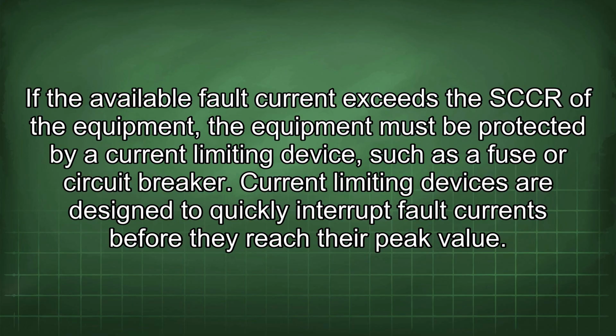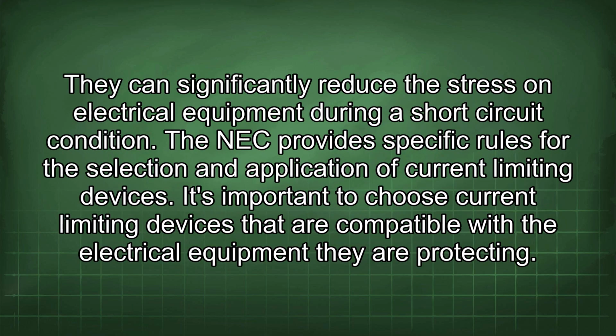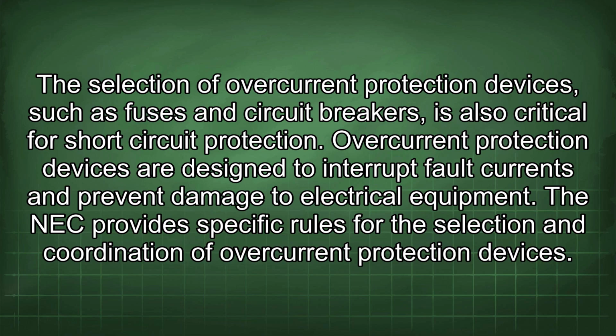Current limiting devices are designed to quickly interrupt fault currents before they reach their peak value. They can significantly reduce the stress on electrical equipment during a short-circuit condition. The NEC provides specific rules for the selection and application of current limiting devices. It's important to choose current limiting devices that are compatible with the electrical equipment they are protecting. The selection of overcurrent protection devices, such as fuses and circuit breakers, is also critical for short-circuit protection. Overcurrent protection devices are designed to interrupt fault currents and prevent damage to electrical equipment. The NEC provides specific rules for the selection and coordination of overcurrent protection devices.